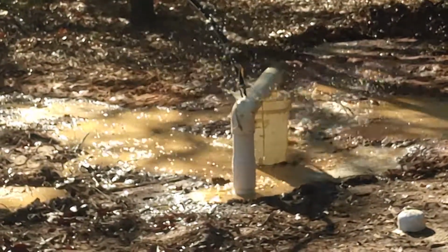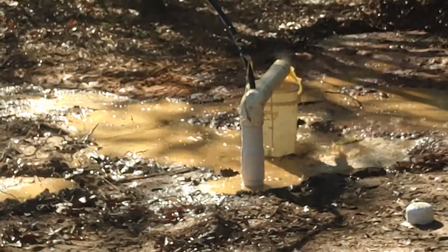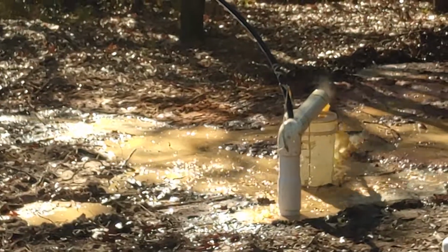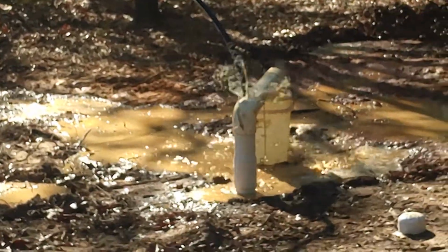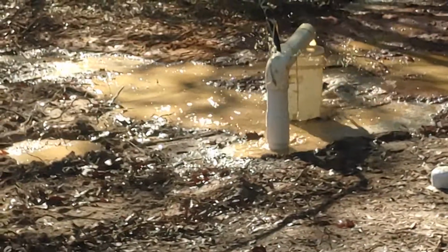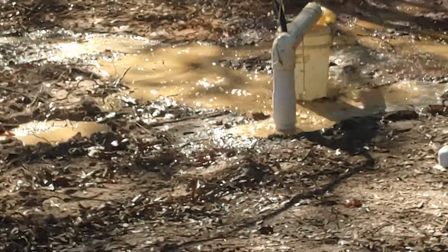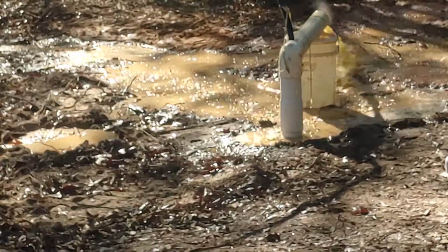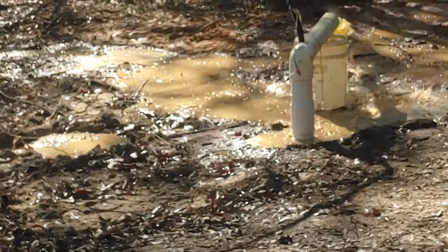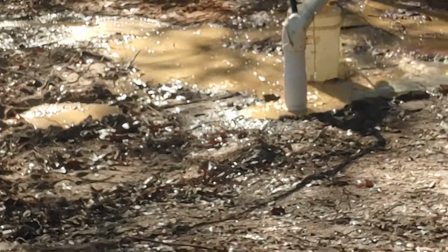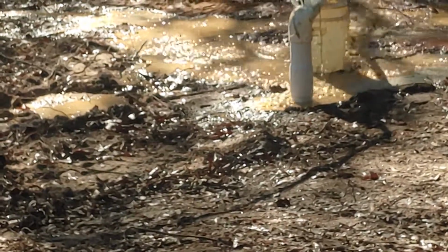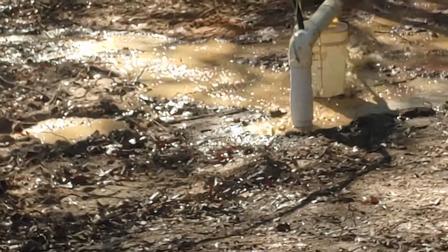Once you get your power, like I said, we come back out. That's part of that bid too, and we do the final setup. Like I said, I can't get 100% of the solids out doing it this way, but we're pumping it out a whole lot better. Once we set the pump, we'll open-ended blow it, let it pump for a little while, then he'll install that cycle stop valve, and then usually we have a customer run them about 24 hours. We'll get a hose off in the woods and just let them run, and it gets everything seated, pulls everything where it needs to go, and gets everything packed in. Gotcha. Then you'll be ready to put it online. And of course in that time you can test it.